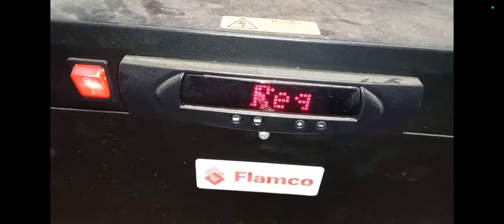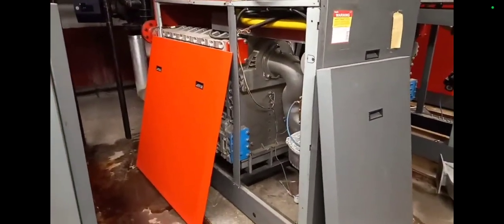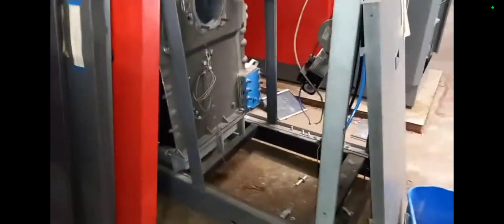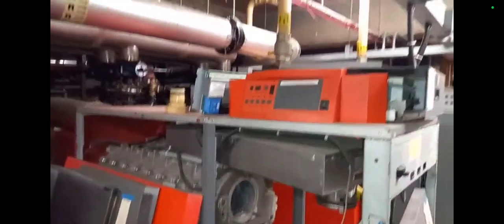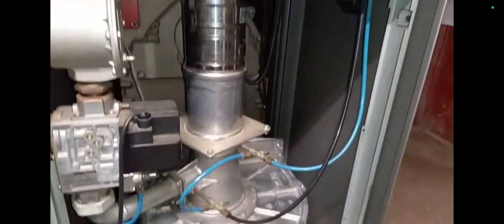This pressurization unit is showing a service is required. You've got one side of the plate, one on the other side, and you can see the boilers here. Boiler one looks like it was decommissioned — it's been isolated, and a padlock's been put on it. I think the padlock's a bit excessive; a cable tie probably would have been good. This one looks in bad shape and parts have been pulled off it. They decided not to padlock boiler two. And there's a fourth one which was also off but not properly off, so I'm going to have a look at that one later.